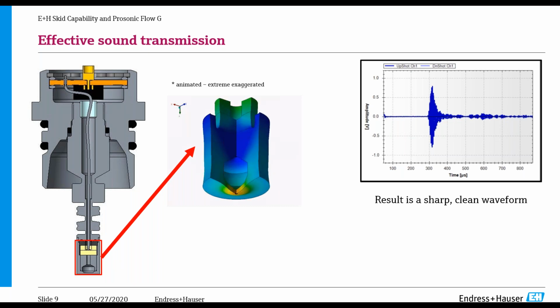So here we go, we see the vibration of the piezos, that energy from the ultrasonic signals being concentrated as it goes around this hollow piece in the middle, and then you get one big kind of trampoline effect of transmitting that sound into the gas. And you can see on the right side, we've got a graphic of the signal waveform, and what we're really looking for is what we have here, which is a nice, clean, quick signal. So you want to get it out quickly.